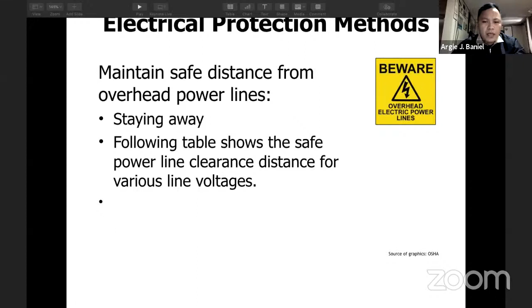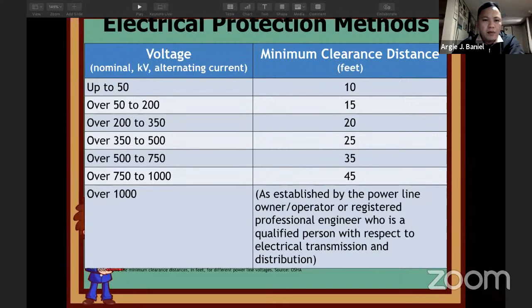Maintain safe distances from overhead power lines. So staying away, following the table shows the safe power line clearances distance for various line voltages. Ito yung mga nasa NFPA 70 and National Electrical Code, but in a Philippine Electrical Code, so i-convert lang natin into meter. If you are working from 50 to 200 kV, there must be a 15 feet. And then for 1,000 kV, established by the power lines in a Philippine Electrical Code, so gamitin natin yan. Over 200 to 350 kV, 20 feet away. So we must follow the minimum clearance distances depends to the voltage or nominal kilovolts and alternating current.